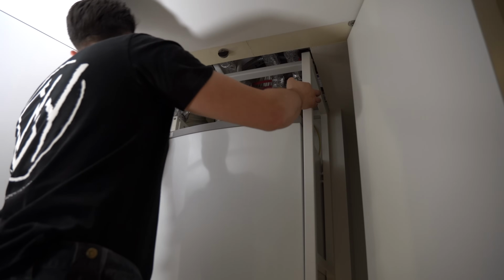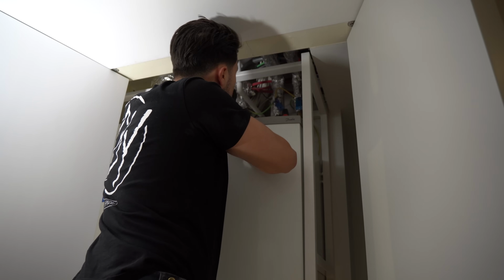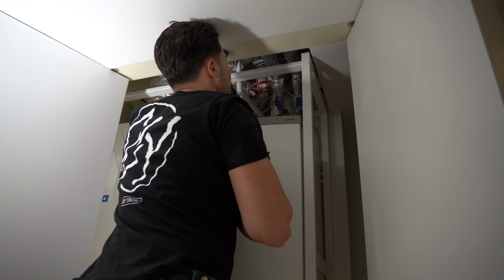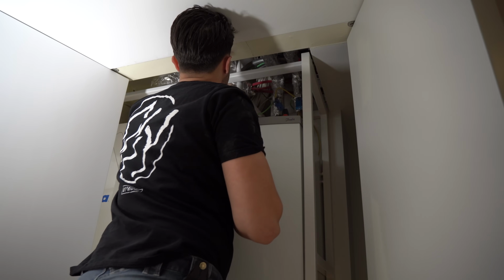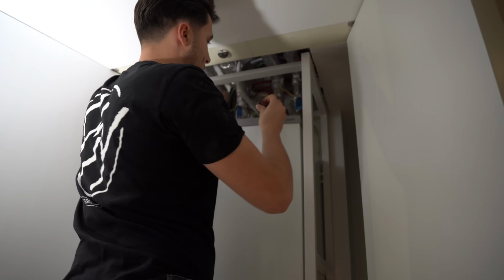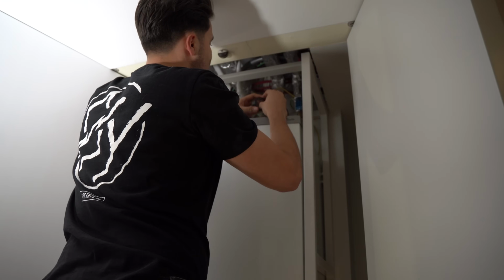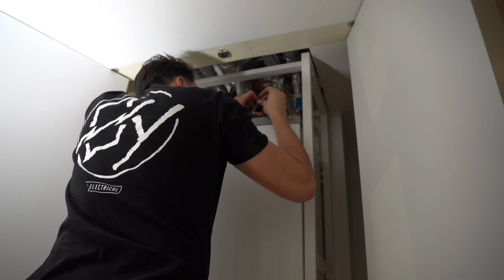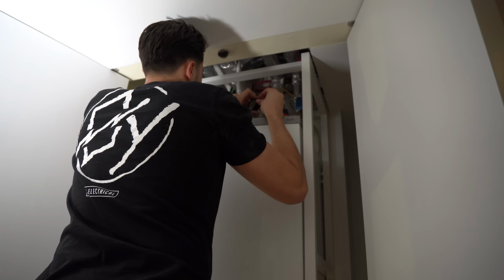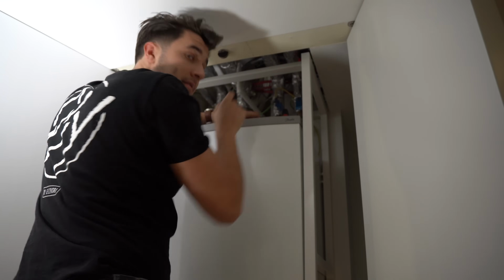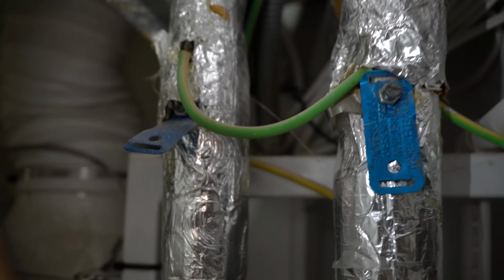Last problem of the day. There's a steel conduit up here that's not being glanded off correctly, but it's going into an open top trunking, and it's a double insulated cable. So I'd argue that the steel conduit itself is not necessary. It is glanded that end, so I'm going to get the camera and show you. There you go. You see, it is glanded off in there, and then it runs along a bit janky down into the top of that trunking back there.